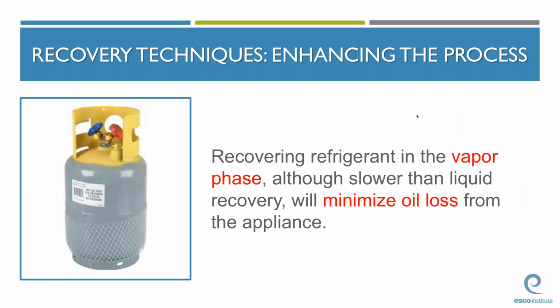Although liquid recovery might be faster, there are times when a slower option is desirable. Recovering refrigerant in the vapor phase, although slower than liquid recovery, will minimize oil loss from the appliance. This is important, for example, when the system repair does not involve compressor replacement. Remind your students that when a compressor is replaced, the new compressor comes with a full charge of oil. So a loss of oil during liquid recovery will have no negative effect on future system operation. This, however, is not the case when the system compressor is not being replaced.